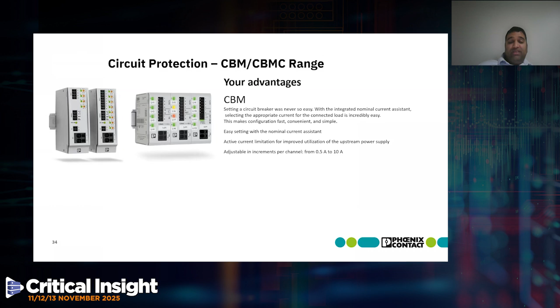Circuit protection is something used a lot in data centers. This circuit breaker is just like a normal circuit breaker, but it allows you to remotely reset, and it's very quick to configure, fast, convenient, and simple. Its ratings range from half an amp up to 10 amps. The advantages are that it can be adjusted tool-free via a single LED push button, and it can be ordered pre-configured for device protection.